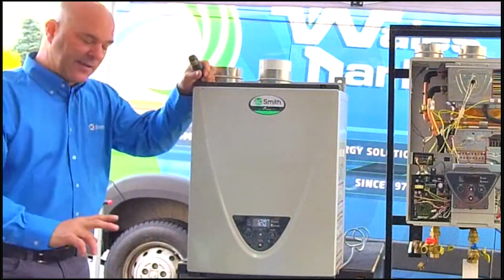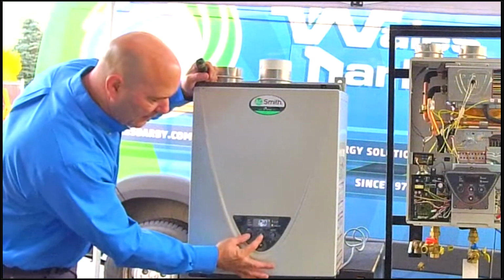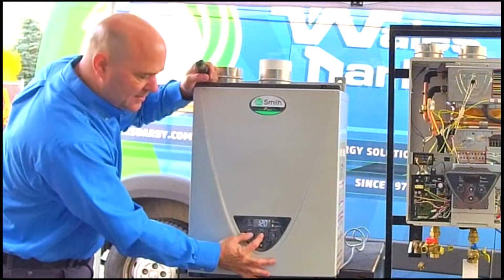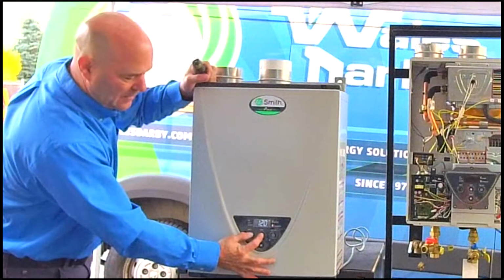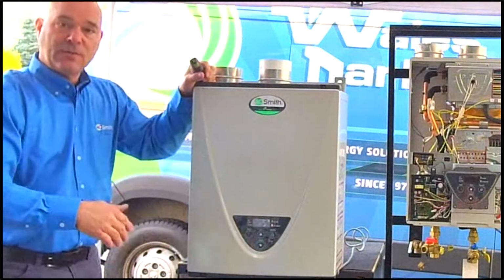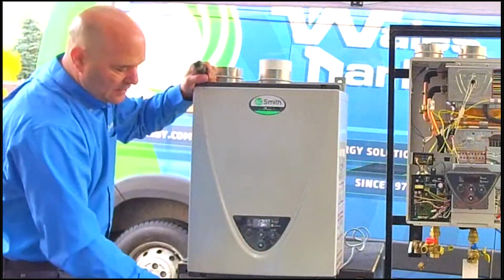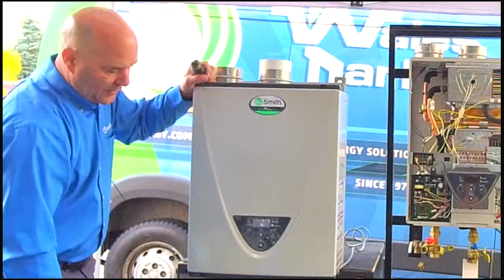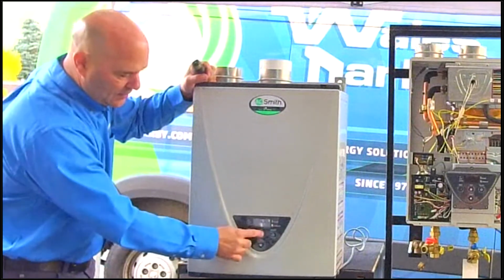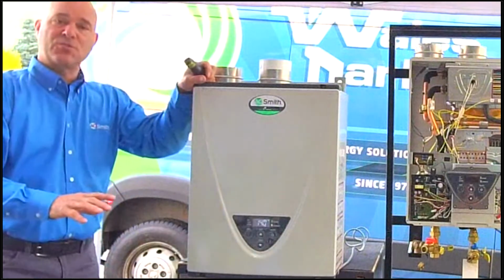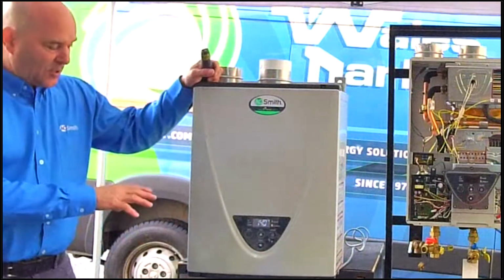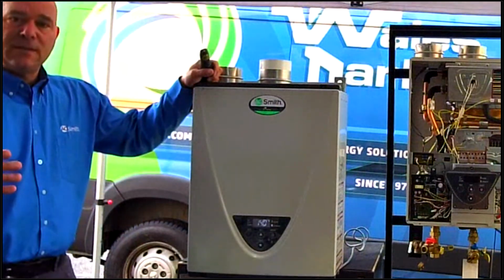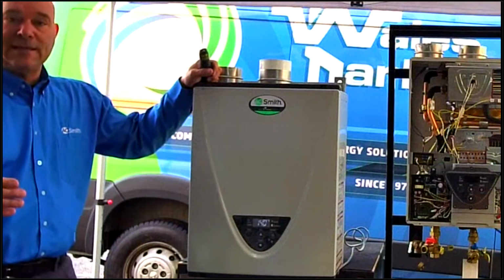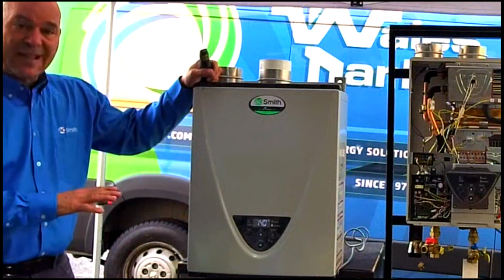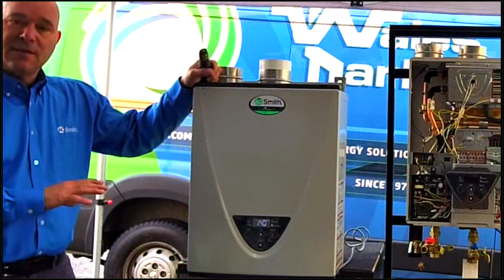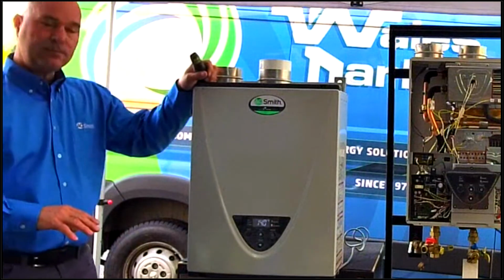If you need to elevate it above 120, you hit the info and hot buttons at the same time and hold them. You see it flashing, it went to 125, 130, 135, 140, and that's it with this control, 140. I can purchase a control that'll get me to 160. I can purchase a control that'll get me to 180. But currently, the standard control that comes out of the box maxes out at 140.